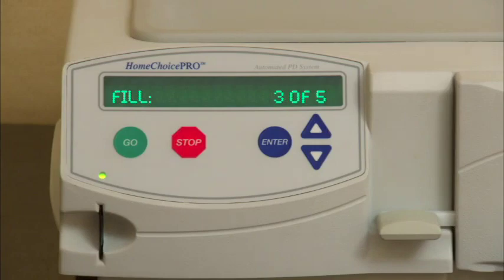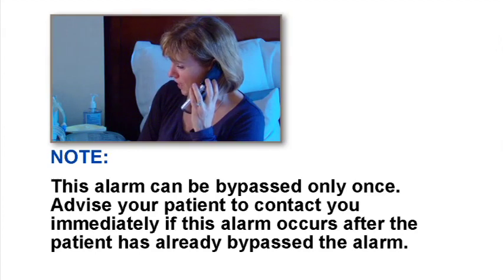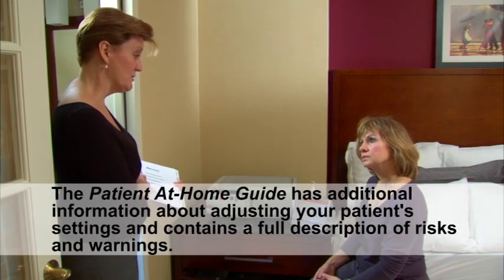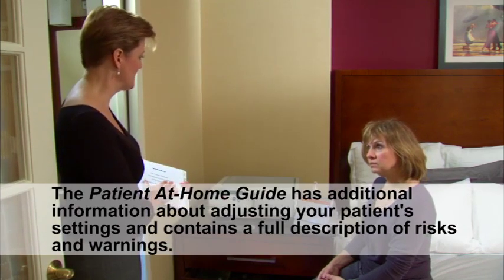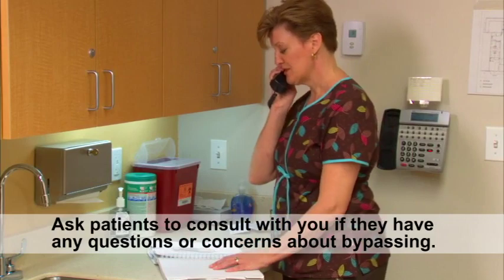The next fill begins and the fill number is displayed on their screen. Note: this alarm can be bypassed only once. Advise your patient to contact you immediately if this alarm occurs after the patient has already bypassed the alarm. Warning: bypassing a caution negative UF alarm can leave fluid in the peritoneal cavity and create an increase in intraperitoneal volume, or IIPV. IIPV could result in a feeling of abdominal discomfort, serious injury, or death. The Patient at Home Guide has additional information about adjusting your patient's settings and contains a full description of risks and warnings. Please review this guide for complete information. Ask patients to consult with you if they have any questions or concerns about bypassing.